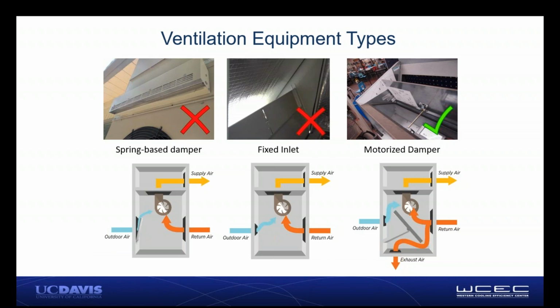The second design is a fixed inlet. So there's a large hole here that allows the air to come in. But one of the issues is that you need to be able to shut that if needed. And the other issue is there's no path for the exhaust air to go out. So if you bring 450 CFM into a classroom, you have to be able to exhaust air from it, because otherwise you would be pressurizing the building.